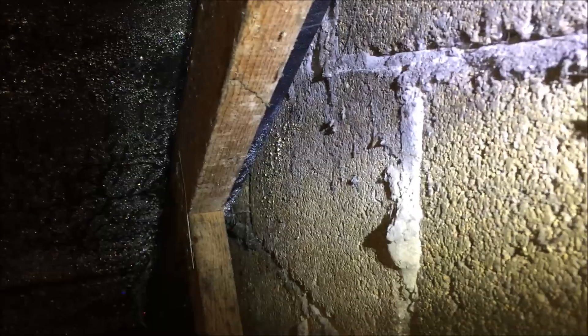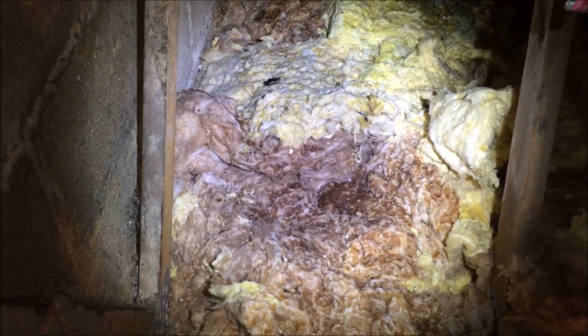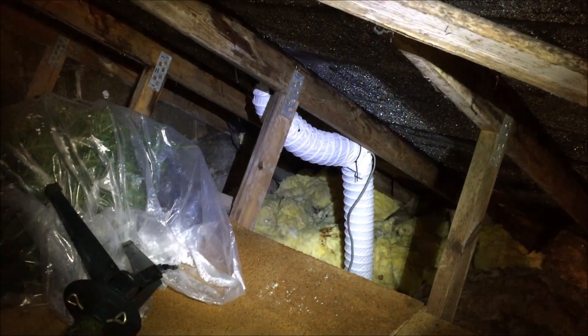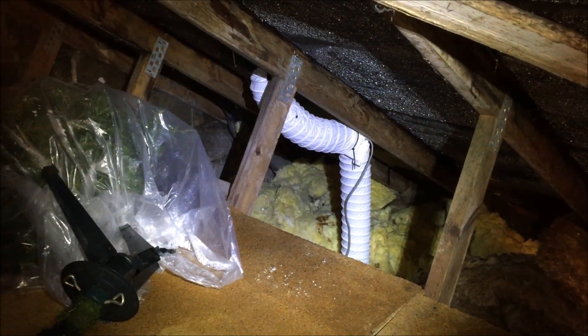If you look down on the gable, you can see it condensing down there. Across to here, the insulation is all wet — there are lots of little divots in it from the water hitting it. Apart from an extraction fan, there's no condensate wrap and no insulation.